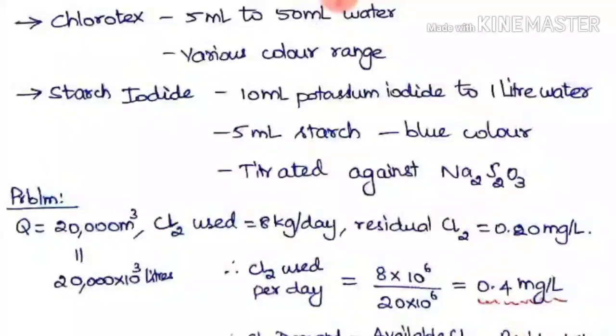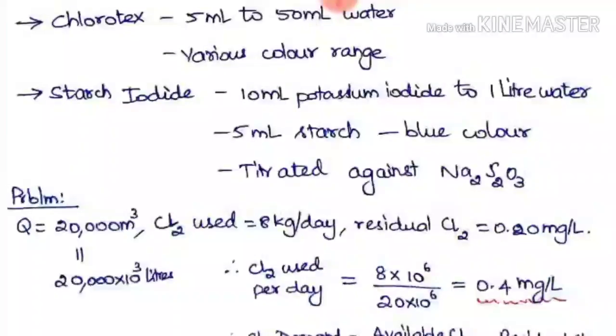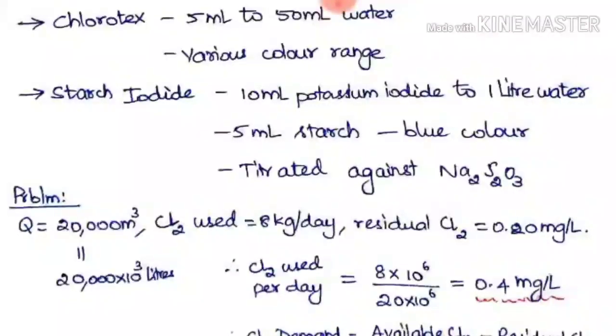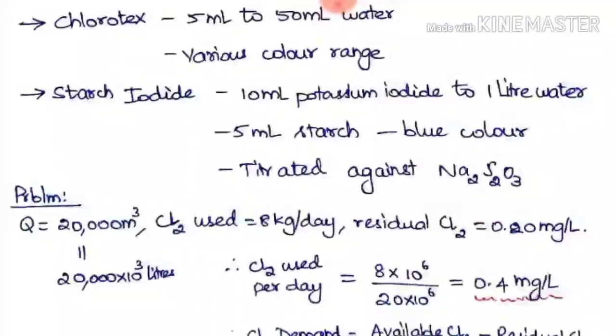Here is an example problem for calculating chlorine demand and chlorine residue. The quantity of water treated is 20,000 m³, the chlorine used per day is 8 kg, and the residual chlorine is 0.2 mg/L. To find the chlorine dosage, divide the chlorine used by the amount of water treated: 8 kg/day divided by 20,000 m³, converted to milligrams and liters.